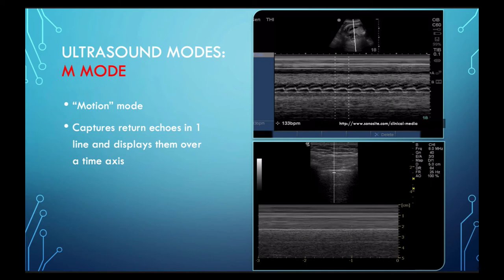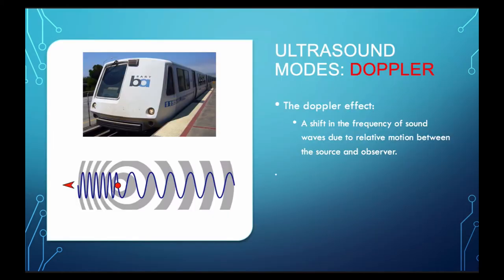We have M-mode, which stands for motion mode. This is a really cool mode because if you look on the screen, you see a white line trajecting through the image. As you put that cursor along a single line within any 2D image, this mode only assesses the movement of tissues along that single line and analyzes it over time. Any movement of structures, including changes of cavity size and movements along that line, can be analyzed. Common clinical applications include the presence or absence of pleural sliding when assessing for a possible pneumothorax, assessing cardiac motion and fetal heart rates, and changes in the diameter of the inferior vena cava during respiration.